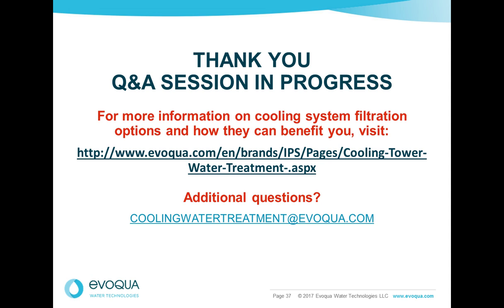and actually, there's a way of doing it where you could have it operate seasonally. Have the coarse one, and I'm calling it coarse, but let's say it's a 50 micron screen during the winter, and your ultra efficient one, your Vortisand, won't need to operate very much, so it'll take some of the burden off. But yeah, I'm with Bob. Oversize your filter, spend a little bit more money, and actually you'll save money by doing it that way. Just put one good-sized one in there. Interesting.